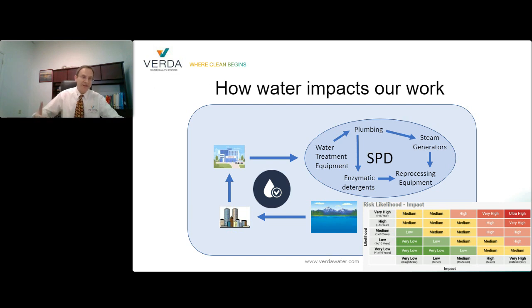The more dissolved solids in the water, the more your reverse osmosis and deionization treatment system must work. DI tank treatments, for instance, may become more frequent. RO membranes may become fouled more quickly and need to be replaced. And if you're not watching and monitoring this equipment closely, and what I mean by that is you're only checking in once a month to see how things are doing, you may miss that the incoming water has changed dramatically since your last checkpoint, and it's impacting the planned PM schedule on your water treatment equipment.